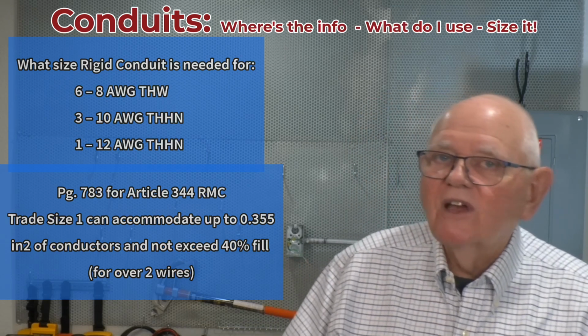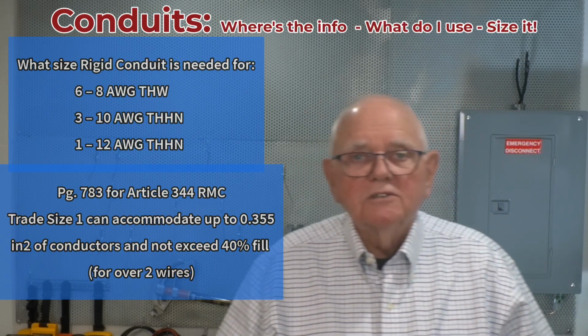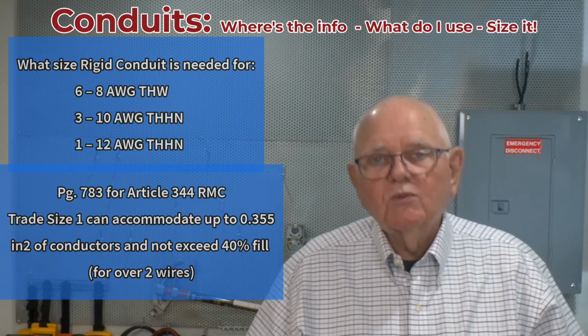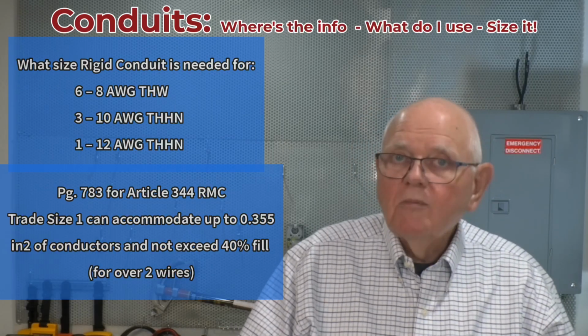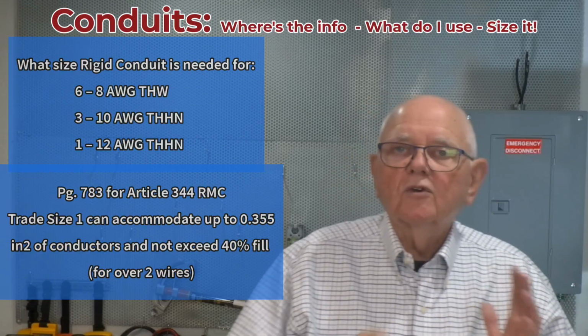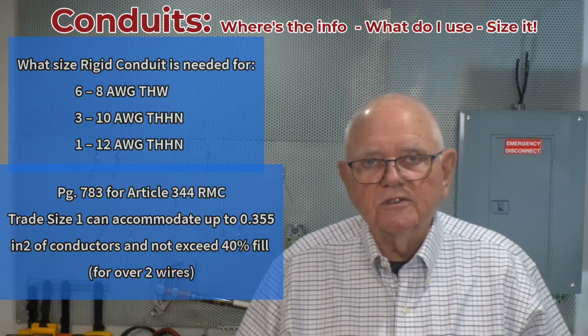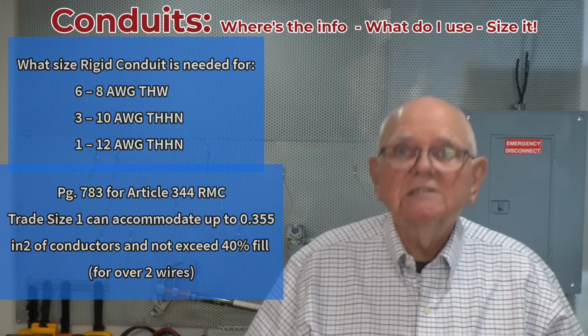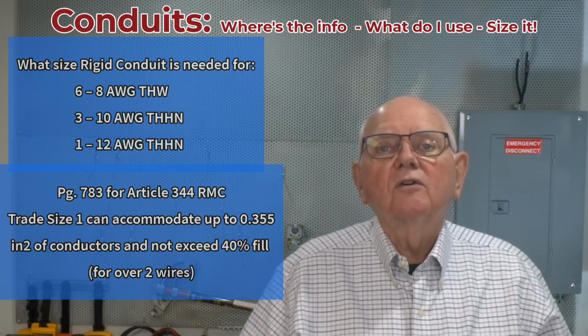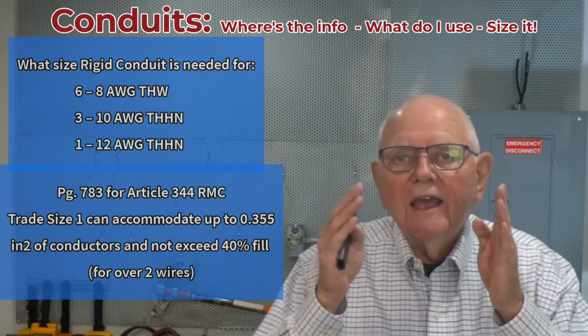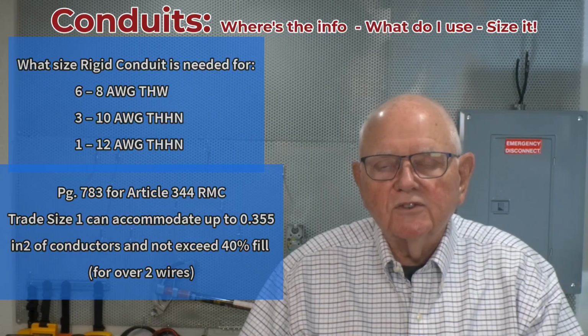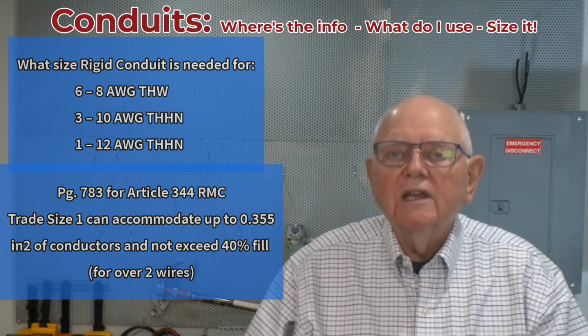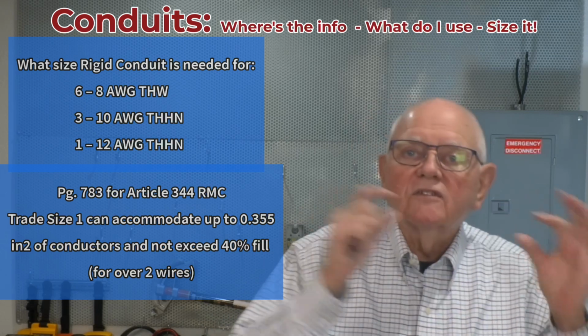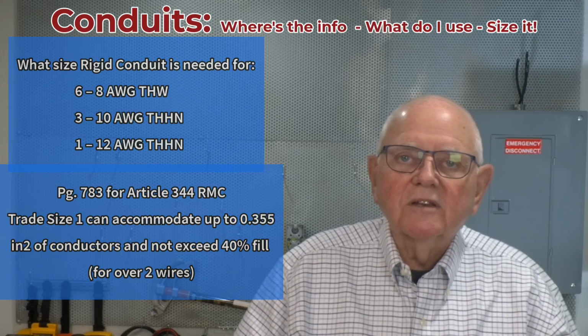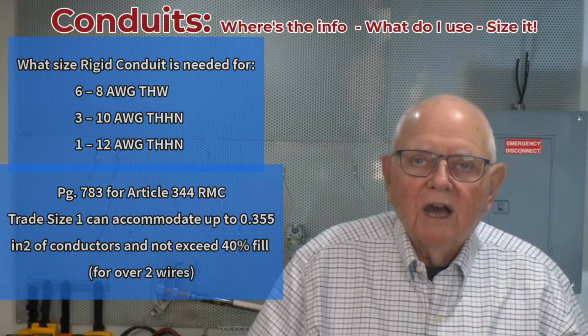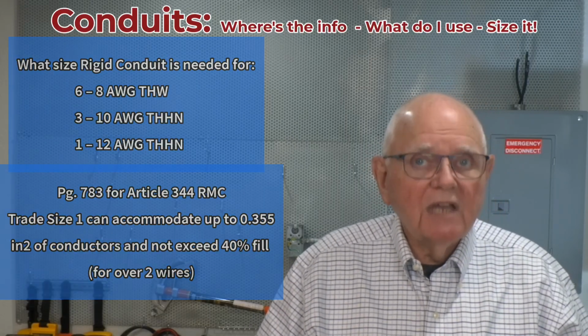So a little bit of practice on that one, but that's how I'm going to determine what size raceway I need. So if all my conductors are the same size, once again, go to Informative Annex C and make life easy for yourself. If they are different sizes, as often happens many times, you're going to have to go to table 5 and add up the areas for each one of those individual or groups of conductors that you're using. Get your total area, take that to table 4, and look up for whatever particular conduit then, what size conduit that you need. So that's how we size our conduit.